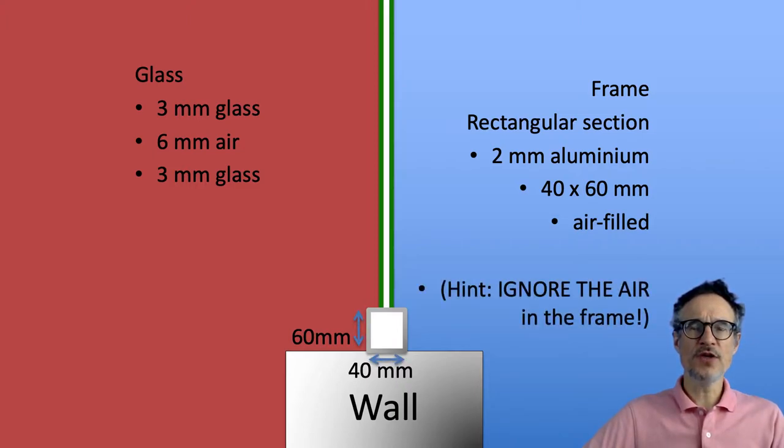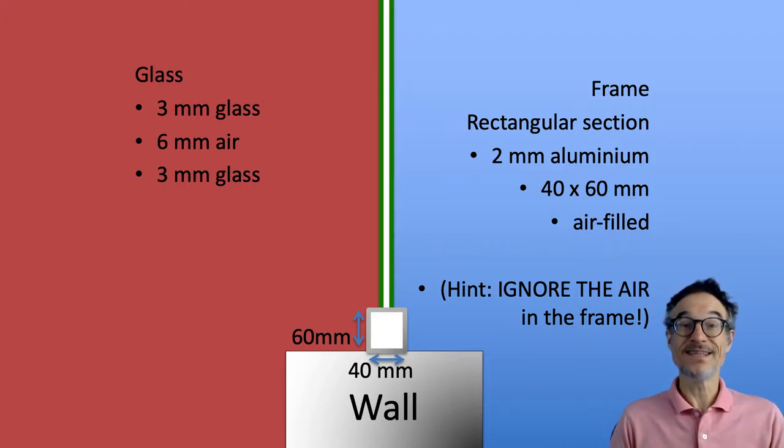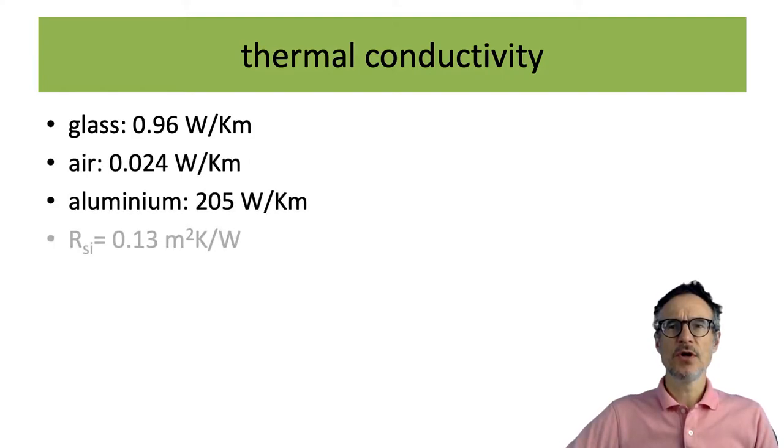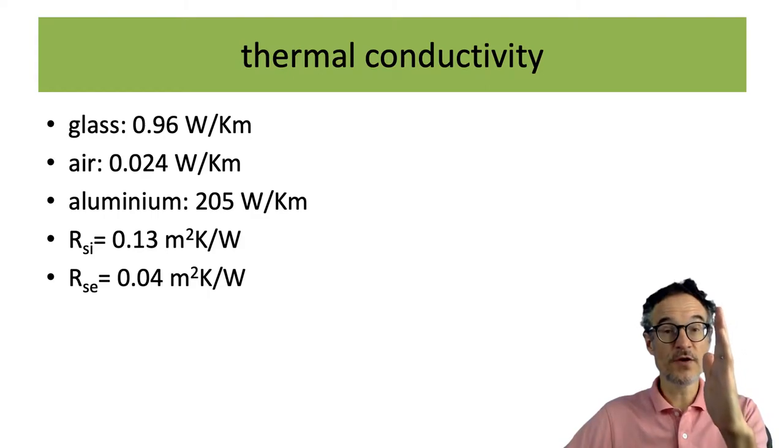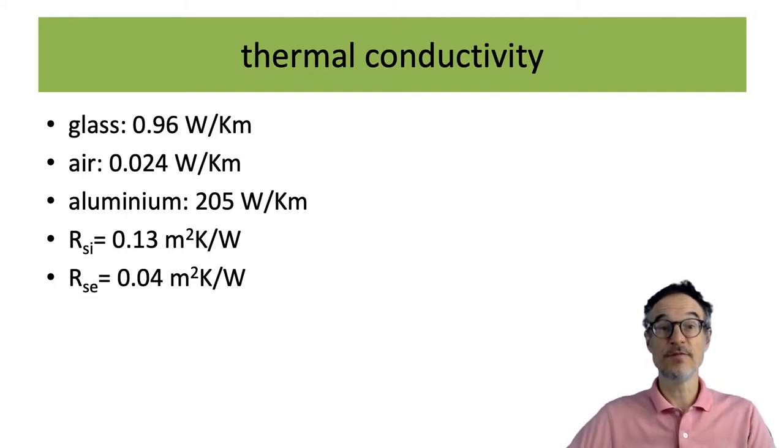When we are doing the calculations, because aluminum conducts much, much better than air, we can basically ignore the air for the calculations, which makes it a little bit easier. So here are the thermal conductivities. And that's the surface resistance on the inside, and that's the surface resistance on the outside. So we have to remember when we have a window, the window is also stopping air on each side, so that's going to have an effect on the insulation performance.